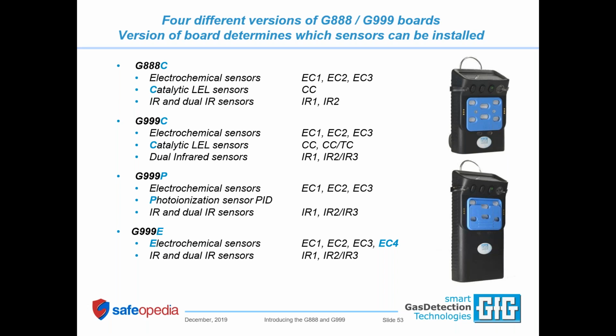And since we have lots of sensor positions available, if you have an IR LEL sensor installed, almost 100% of the time we're going to strongly urge our customers to include a substance-specific hydrogen sensor in the instrument, because that is the one major LEL gas that you run into all the time where you can't ever measure it with an IR sensor. You need to measure it with a different type of sensor. So we do that, and we don't depend on the bad characteristics of a more broadly sensitive, lower cost CO sensor to pick up the hydrogen.